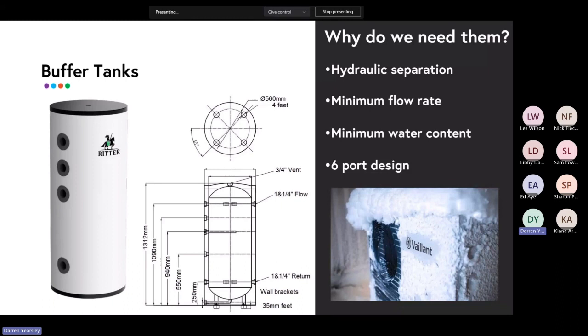You've just got heat pump number 1 running, and that populates the buffer with 65, 70 degree water. And then we pump out of that buffer to a plate heat exchanger, and then your storage tanks go through the plate heat exchanger.